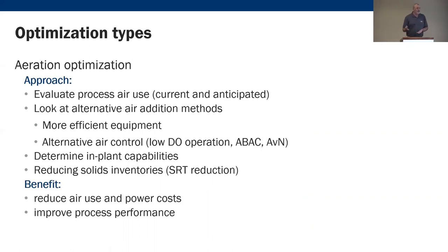Jose Jimenez was doing some incredible work with aeration optimization. Traditional thinking says your DO needs to be at 2 mg/L or your nitrification drops off dramatically. But he and his team are finding that's not necessarily true. We can run these plants at lower dissolved oxygen than the traditional textbook will tell you, and the biomass actually adapts.